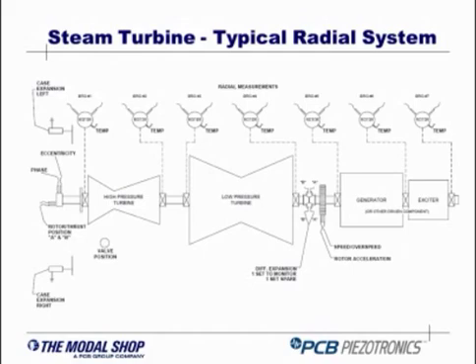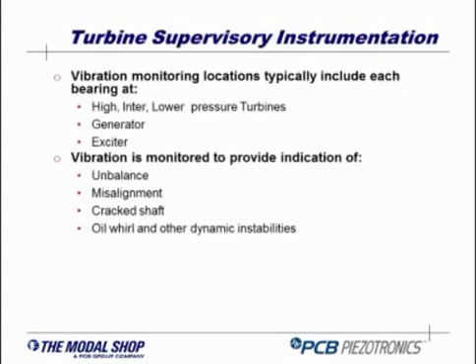So you can measure not only the dynamic displacement, but also with the X and Y you can tell the orbit. You can measure the orbit and how the shaft is moving. So again, this is just a description of the typical locations where you will find the proximity probes in a turbine supervisory instrumentation. And you're checking for all sorts of problems and things that can happen, like unbalance, misalignment, and cracked parts and shafts, and also other dynamic instabilities.